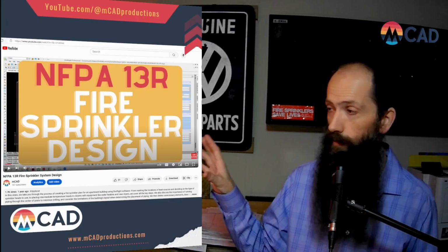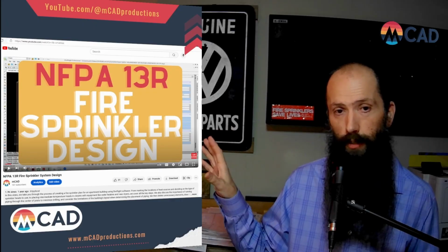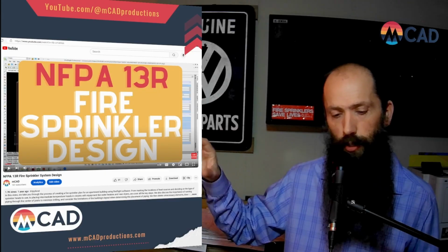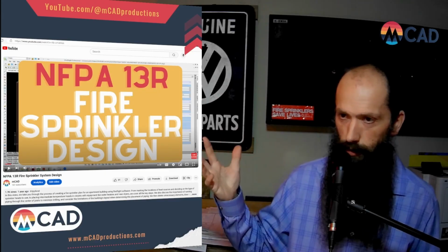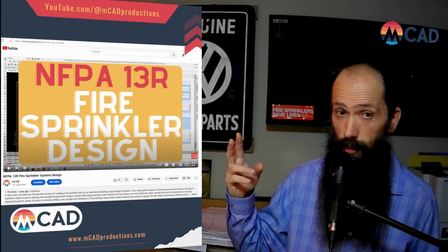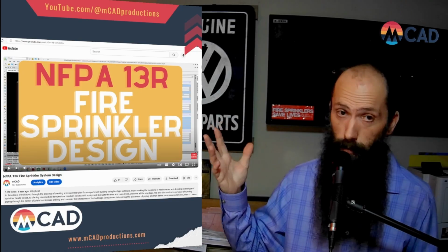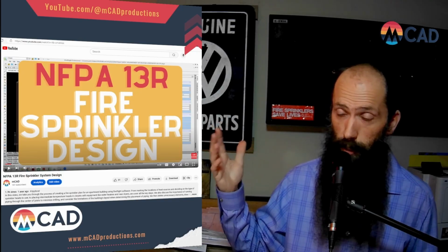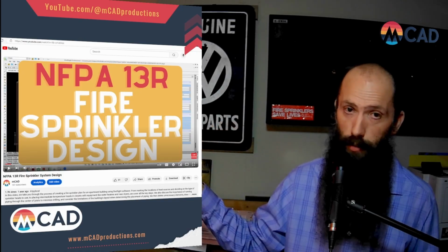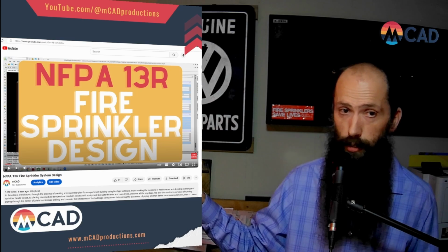The reason that we have that little smaller 13R is just a simple step. It's a single story. It's only 3 units. 13D is up to duplexes, single family and duplexes. So when you get that third unit in there, that makes it a 13R.